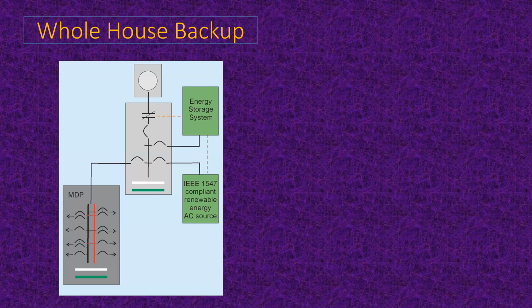Here's just a basic one-line diagram of how a whole house backup system might work. The key is that set of normally closed contacts you see in the middle. Let's see, I wonder if maybe you can even see my cursor if I point at it. I'm going to point at it, and I'm also going to say where I'm pointing. This is the fancy control box here. And when utility power is lost, those contacts open and disconnect the structure. Let's call it a residential house, whatever, but this can be larger scale as well. Most of these systems are scalable up to close to 100,000 watts. So we'll be talking in the 10,000 watt range today, but it's possible to do better than that.